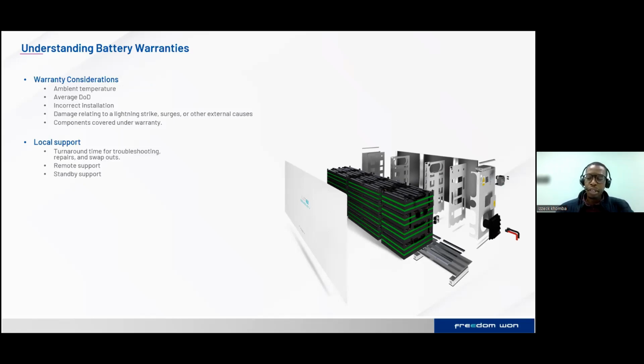So normally the warranty specifies the battery environmental conditions that one needs to take into consideration. Then your average DOD, which is your depth of discharge. The battery manufacturers specify up to what percentage the battery should be discharged on a continuous basis or on a daily basis. Then some batteries specify that the battery can be discharged to a DOD which is even higher than what is stipulated on the data sheet.